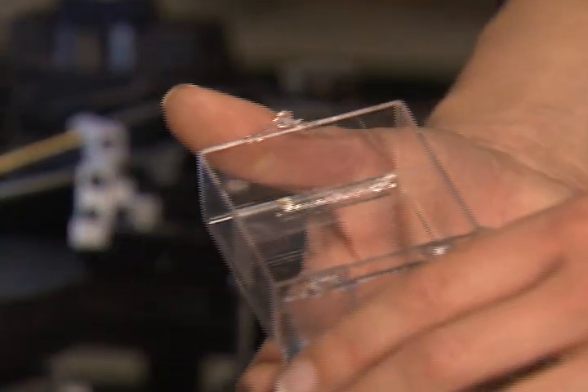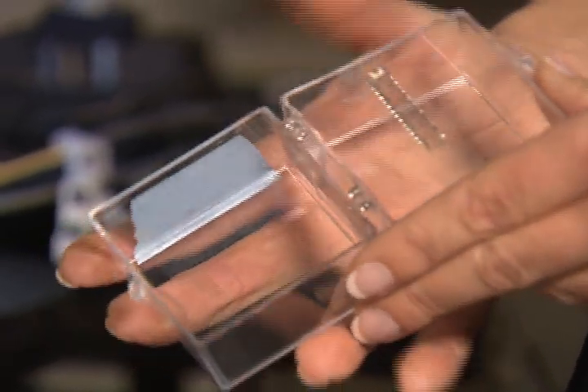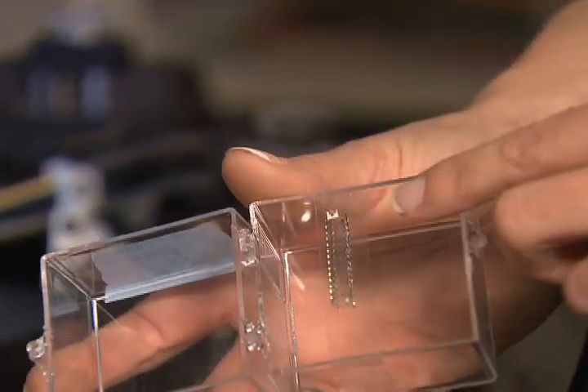This way it can be done once a day, and it doesn't have to be something performed every minute of the day — the device does it for the person. Another very interesting thing about our device is that a lot of medical devices are battery powered, but our device is powered with RF power, making it wireless as the stent acts as an antenna. Therefore we don't need a battery, and the device doesn't have a lifetime per se.